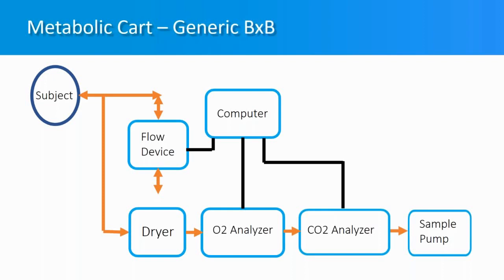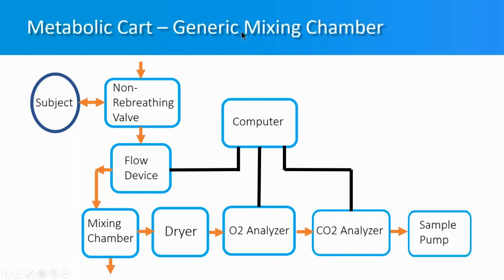There are two types of metabolic carts: the breath-by-breath system and the mixing chamber system. In the breath-by-breath system, the gas sample is drawn directly from the subject's mouth to be analyzed by the gas analyzers, while the subject expires to a flow device to measure flow. Mixing chamber systems add a non-rebreathing valve and a mixing chamber. The non-rebreathing valve allows only expiratory air into the mixing chamber, which mixes the expiratory air for a more homogeneous sample, and the gas sample is then drawn from the mixing chamber.